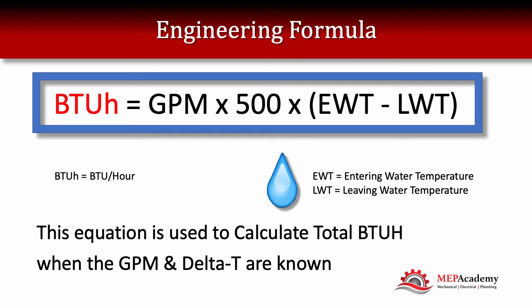I'm going to show you how to calculate the total BTUs of water. This can be used on anything where you can measure the flow and the Delta T. The formula is BTUs per hour equal your GPM — that's your flow of water — times 500, which is a constant, times your entering water temperature minus your leaving water temperature.